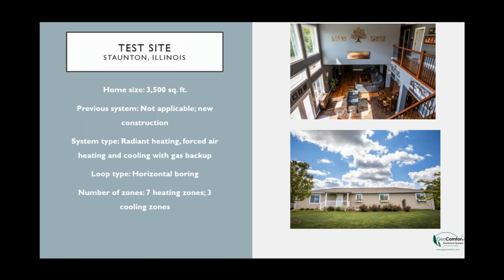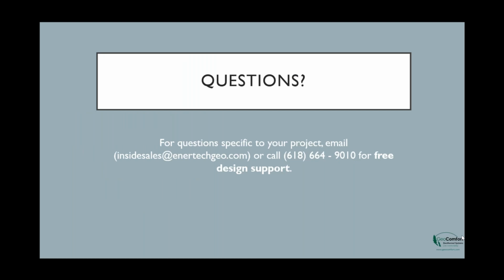But we've got a radiant heating system throughout. Forced air heating is for the shoulder seasons again, and also for cooling. It does have a gas backup system. We've got a horizontal bored loop field, so we drilled directionally or horizontally, roughly 20 feet in the ground. There's about 7 heating zones, 3 cooling zones, and the domestic hot water. And also the garage on this home as well. So another great testimony of how well this product works, how flexible it is, and of course how energy efficient it is.